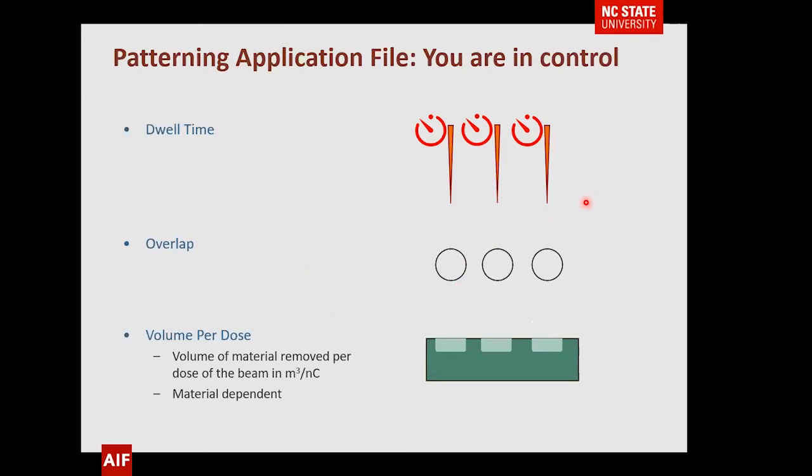One of the things you're going to use in the FIB when you determine your material removal is a patterning application file. There's a lot of information in that file about beam size and beam parameters, but you can typically change three values: the dwell time, the overlap, and the volume per dose. The volume per dose has been calculated and a lot of equipment comes with pre-calculated values, but a lot of people use different materials — different ceramics and such. You may find your ceramic removes very similarly to sapphire or silicon, but if not, you can certainly determine what that volume per dose is.